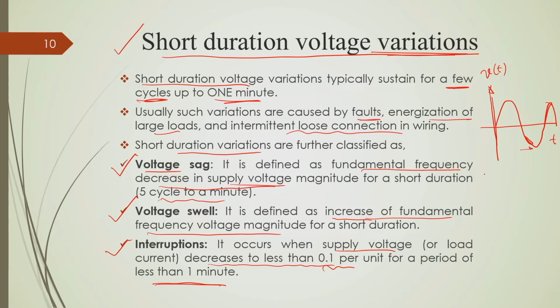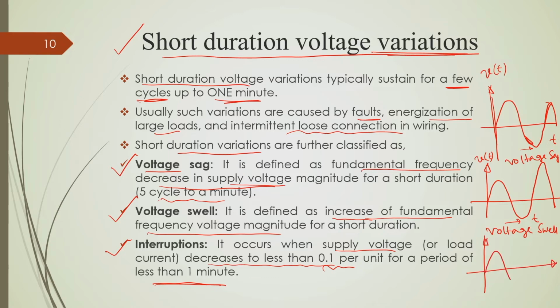Okay. Now, voltage swell means suppose this is your fundamental voltage, and for a certain number of cycles this voltage rises and lasts for a few cycles; then it is called voltage swell. So, this is voltage swell, this is voltage sag. And interruption means suppose this is your fundamental frequency voltage and it becomes almost 0 for a very short period of time; then it is a voltage interruption. So, this is V t, this is time. With this figure you can see how voltage sag, swell and interruption look if you trace out the voltage waveform.